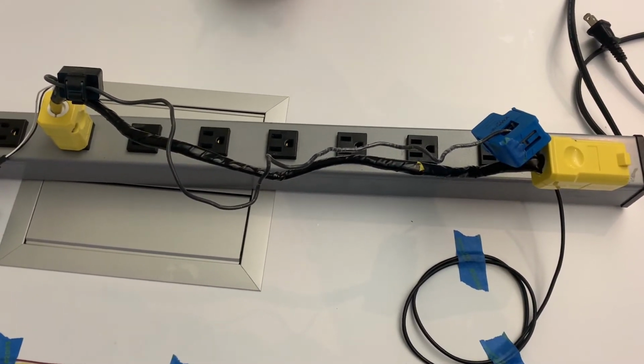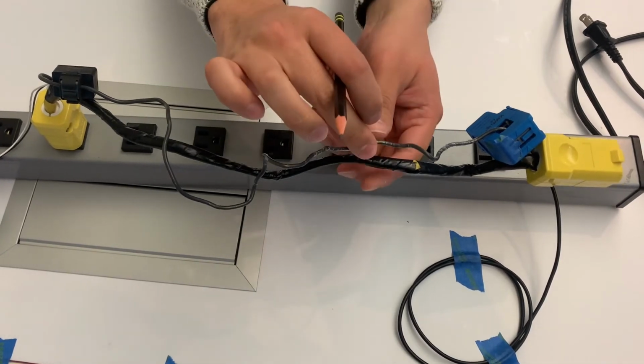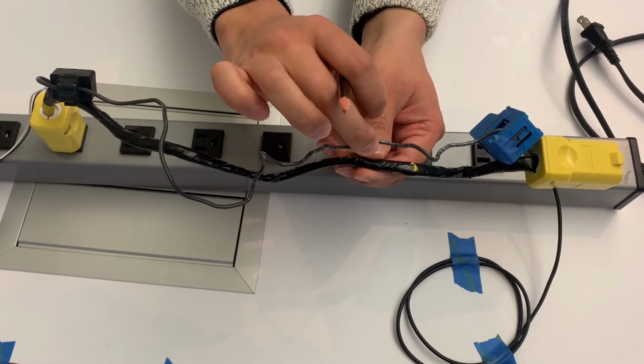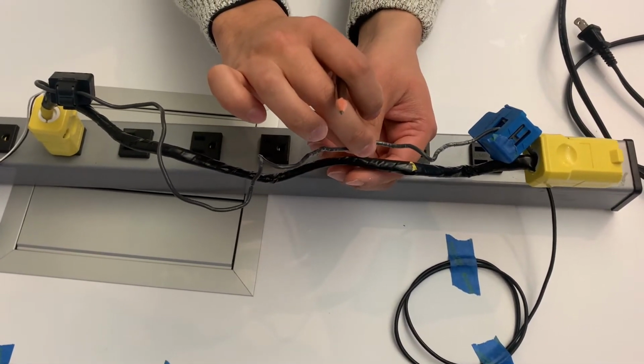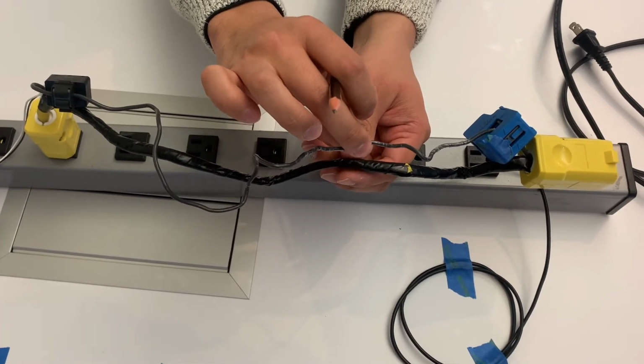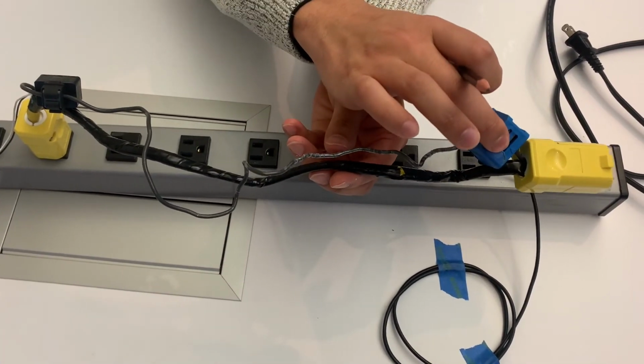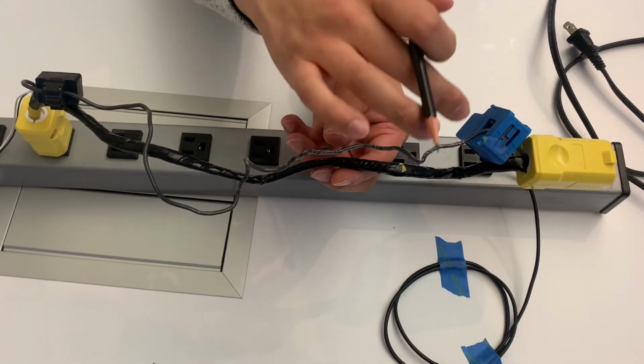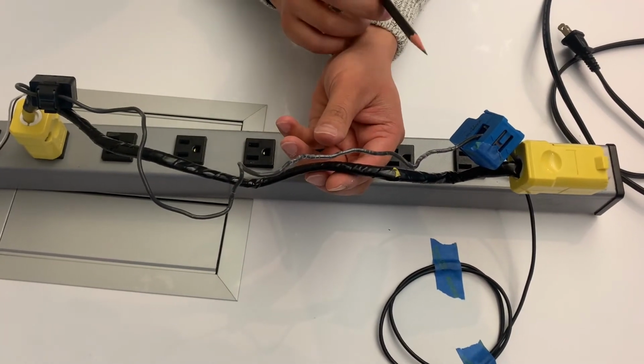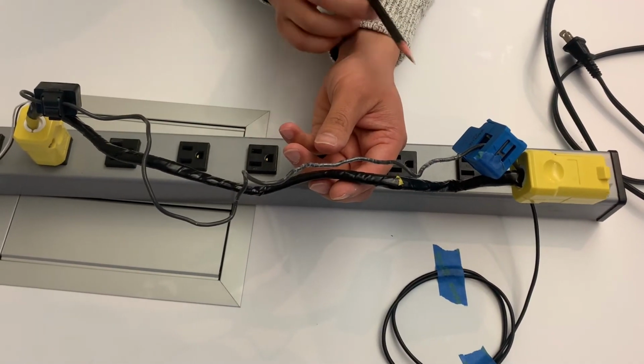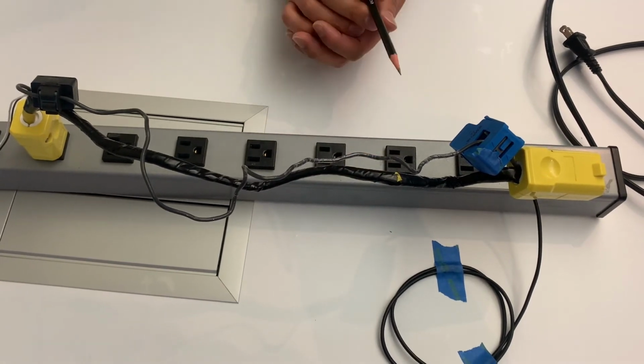The first step to do this is to isolate one of the conductors in the low voltage power line. We have to do this because the magnetic fields will mostly cancel each other out if we just snap the harvesting current transformer around the entire wire wrap, because there are two wires and the current is heading in opposite directions inside the wire wrap.